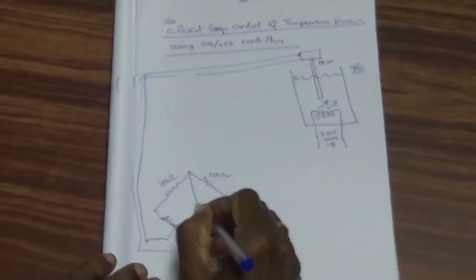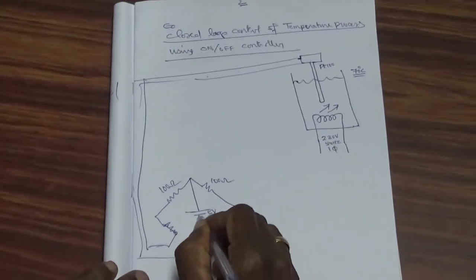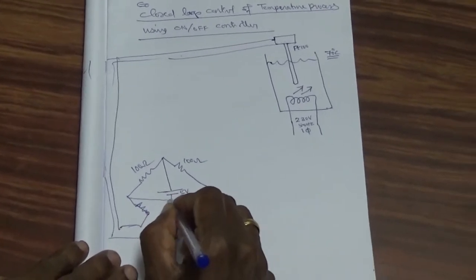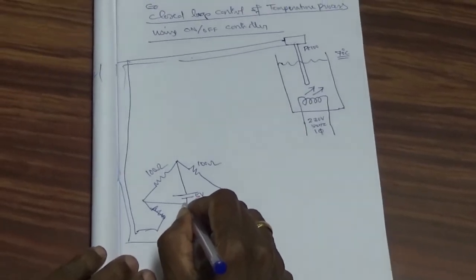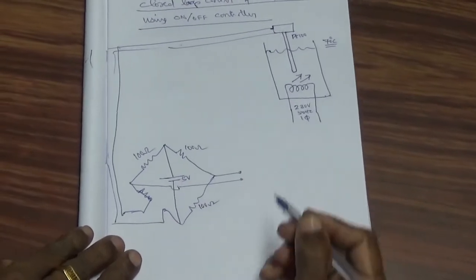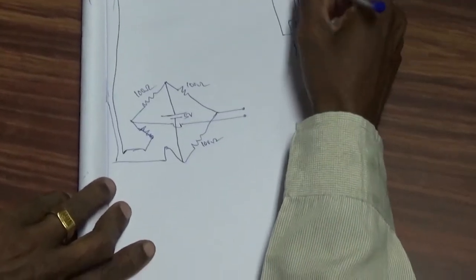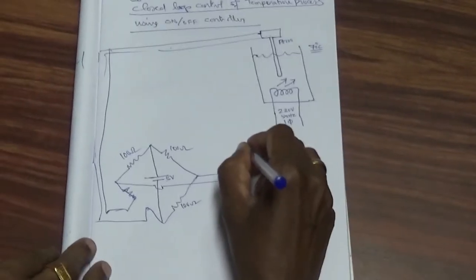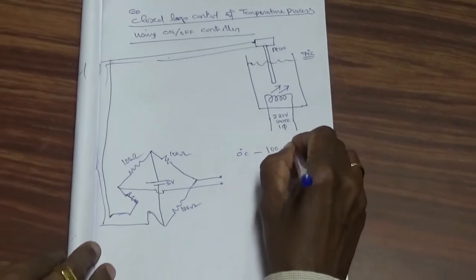A 5 volt DC power supply is connected to the bridge, and two terminals are taken across the opposite corners. The bridge output is available across these terminals. The resistance of PT-100 varies according to temperature. At 0 degrees centigrade, the resistance of this RTD is 100 ohms.